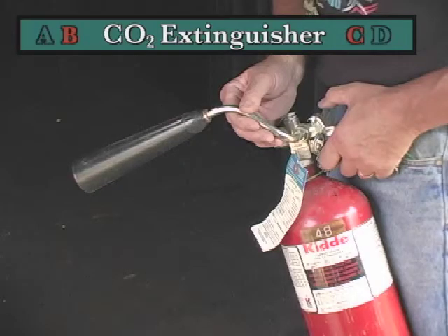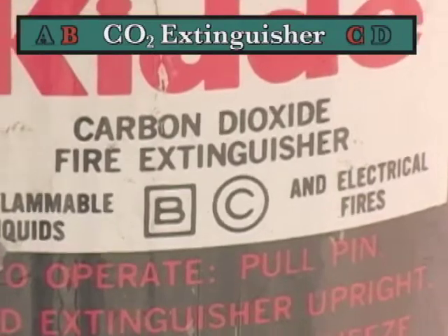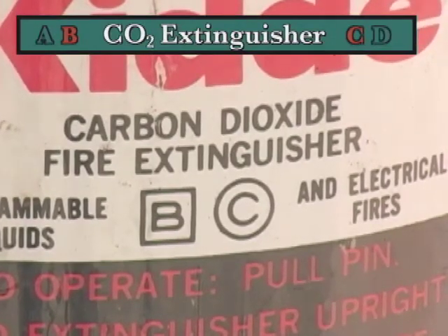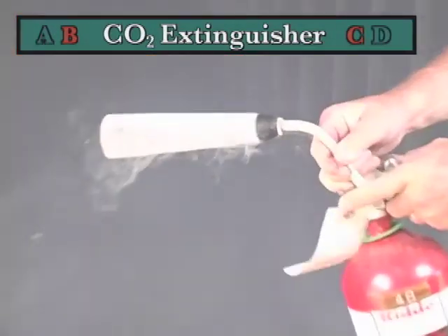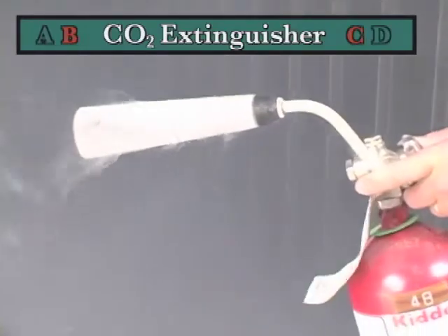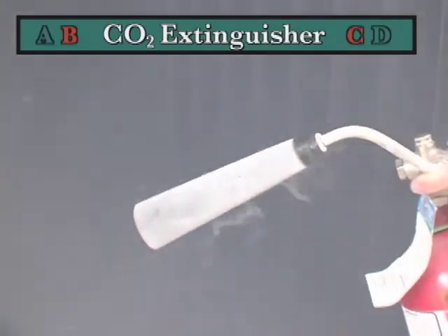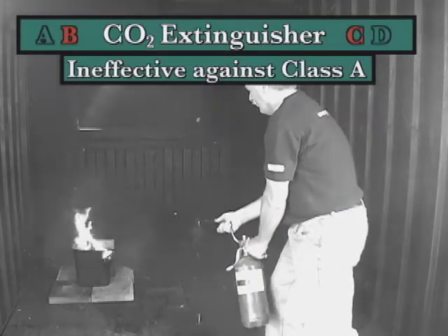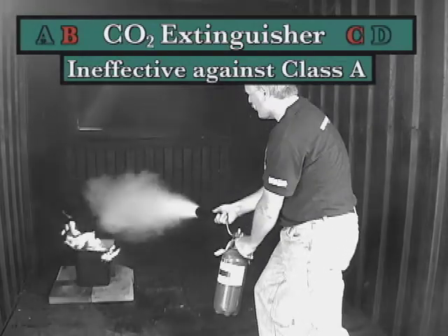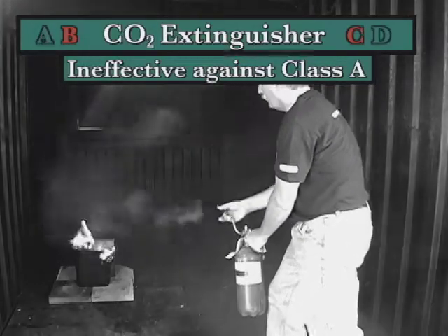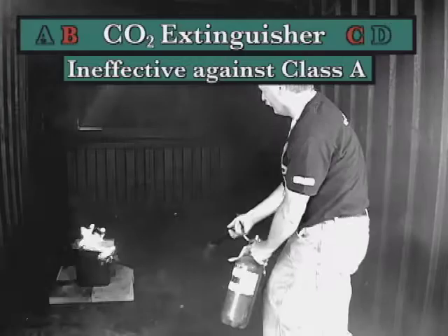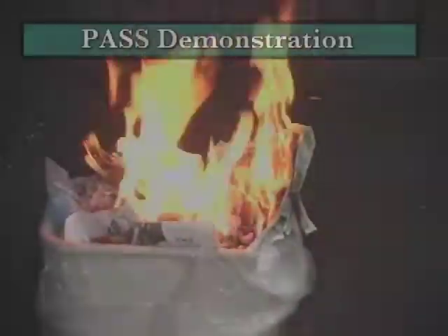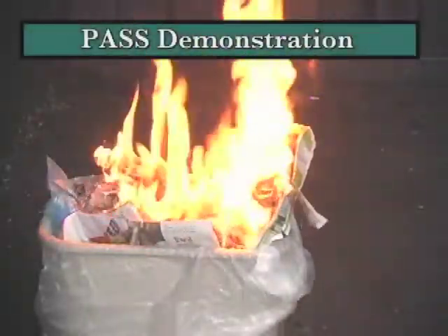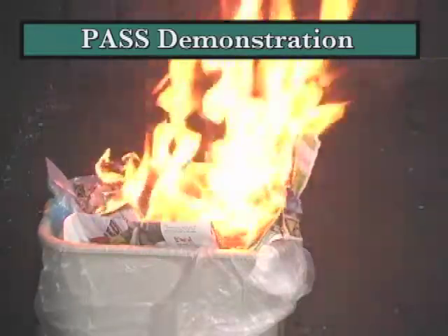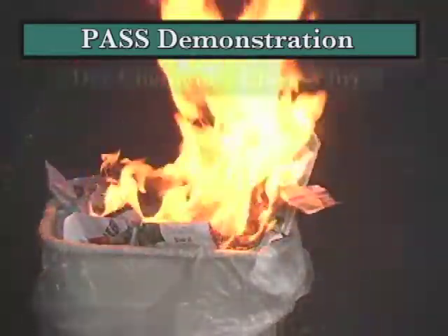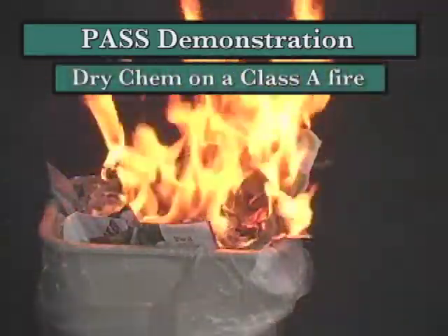Carbon dioxide, also called CO2 extinguishers, are used for Class B and C fires. CO2 extinguishers contain carbon dioxide, a non-flammable gas. They don't work very well on Class A fires because they may not be able to displace enough oxygen to put the fire out, causing it to reignite. For our demonstration, we'll use an extinguisher to put out a fire in a wastebasket, which is a Class A fire. We'll use a dry chemical extinguisher.